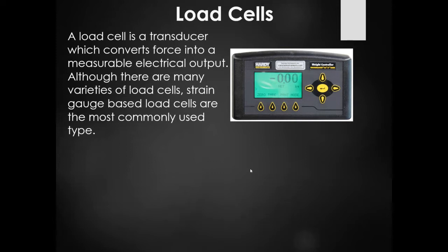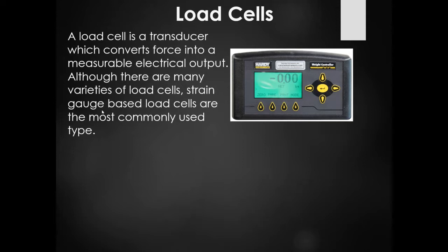Load cells are based off of strain gauges, which basically use a thin piece of wire. When you apply force to it, it gets longer and thinner, increasing the resistance. When the weight is off of it, it gets shorter and thicker, decreasing the resistance. By measuring the change in resistance, we can derive weight out of it.